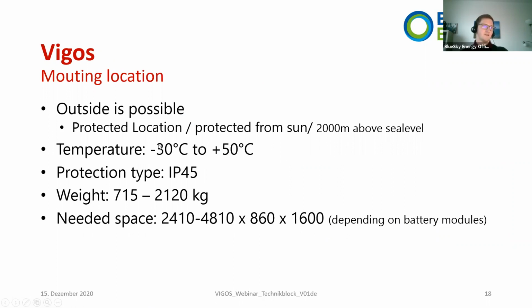Temperature range goes from -30 to +50. We have a protection type of IP45, so really high standard already. The weight, depending on the system size, on the battery and the carbo cap modules, goes from 715 to 2,120 kilograms. And the needed space also depends on how many battery modules you have. The smallest size is 2.4 meters and goes up to 4.8 meters, times 860 millimeters in depth and 1.6 meters in height, depending on the battery modules.